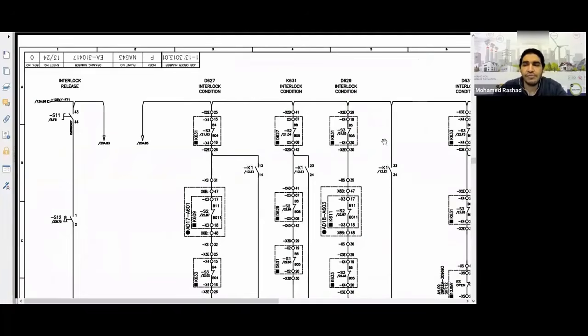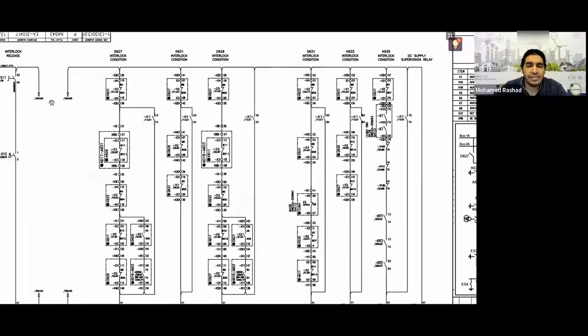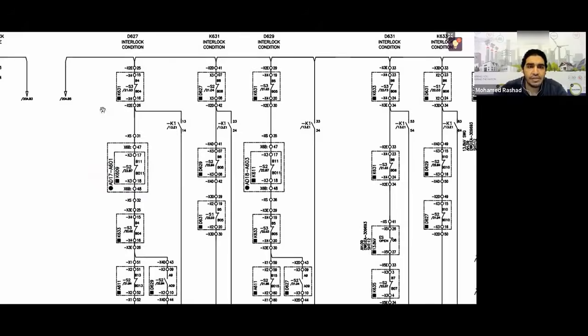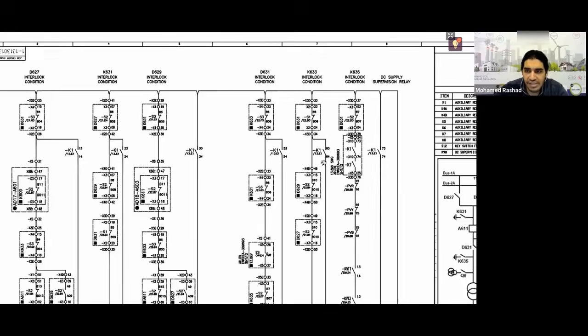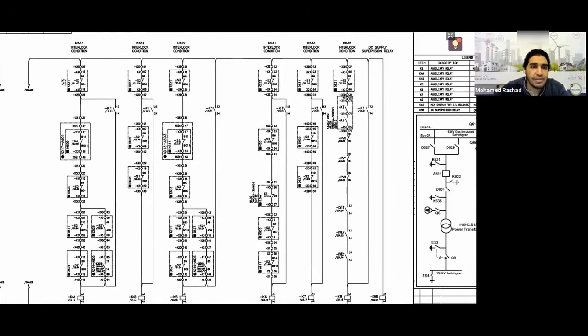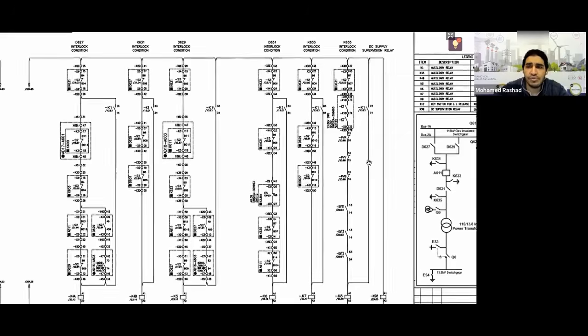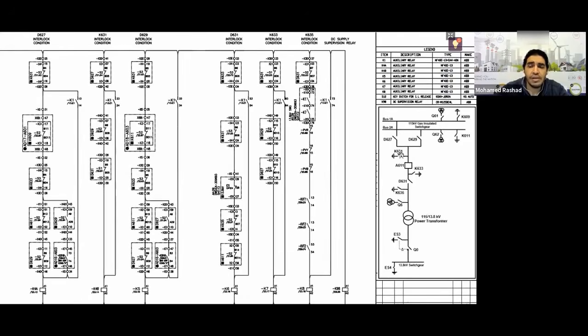Of course, we have now finished the interlocking specific to the D627. If you look at the D627, you will find here it says K631, and a normally closed contact is missing from it. We agreed that all the disconnectors, the disconnector air switches, are drawn in the drawing as if they are open, so all the contacts related to them are drawn with the disconnectors in the open position. So you have K631, which refers to what? Key 631, here it is, should be open, and then it goes down here below.